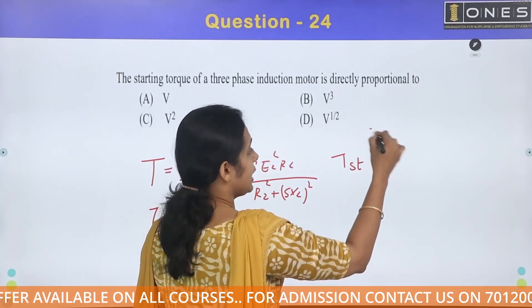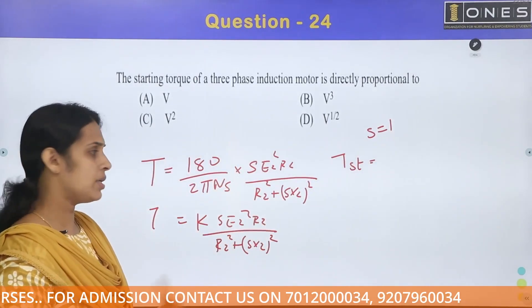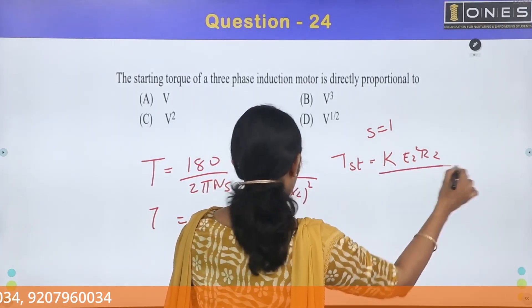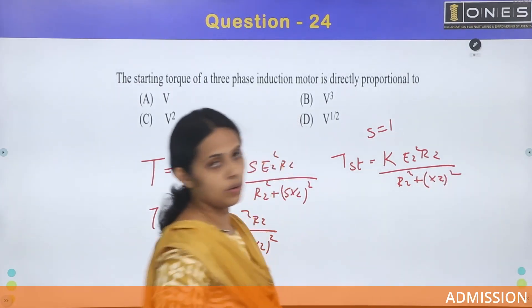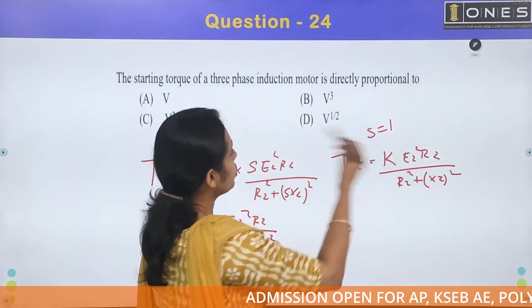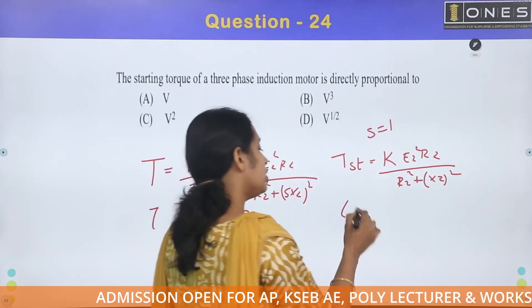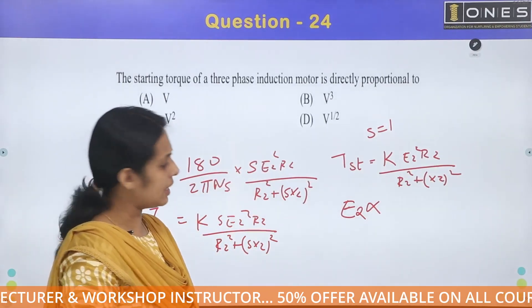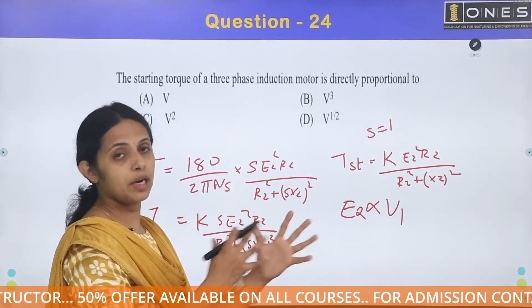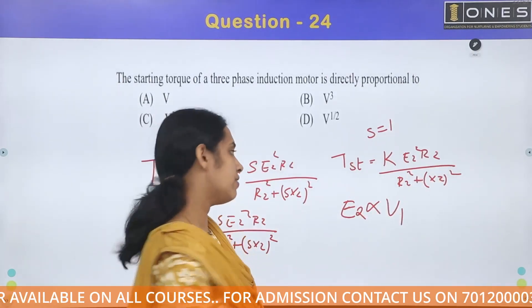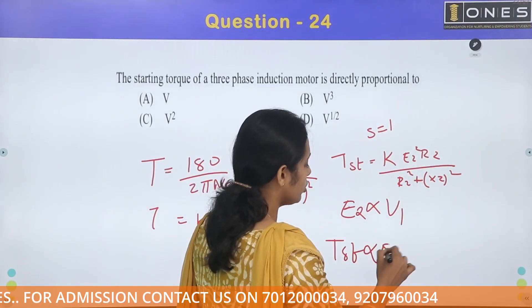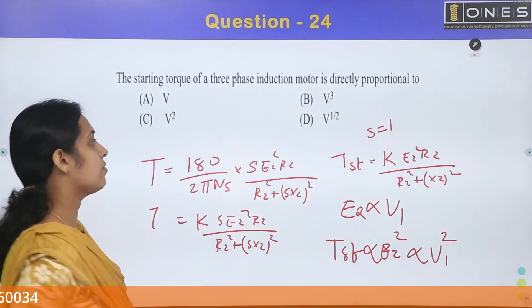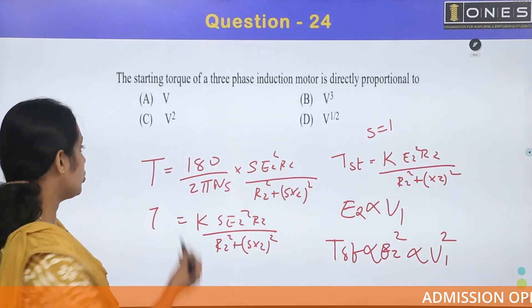For starting torque, s = 1. Substituting s = 1, starting torque = k × E2² × R2 / (R2² + X2²). Starting torque is proportional to E2², where E2 is the induced EMF in the rotor circuit. By the induction motor mutual induction principle, E2 is proportional to V1, the input voltage — similar to transformer principle. So, starting torque is proportional to E2², which is proportional to V1².